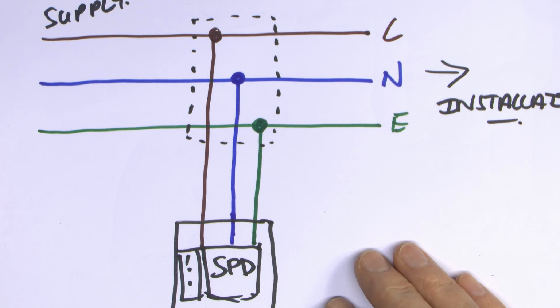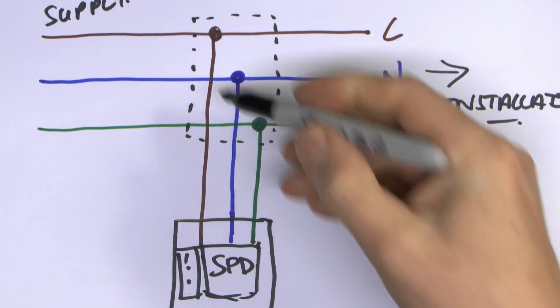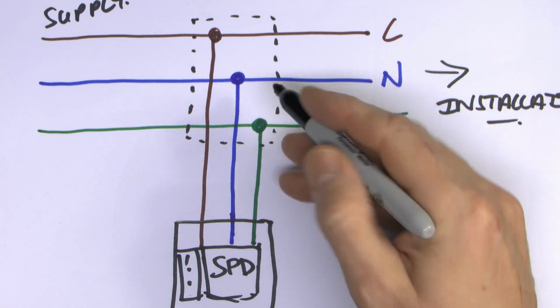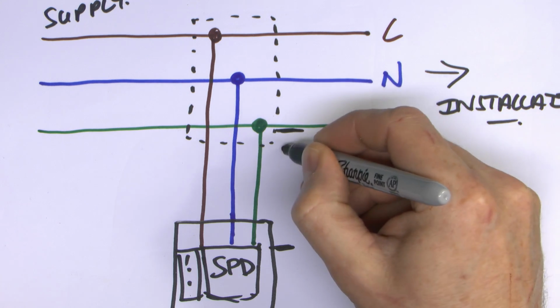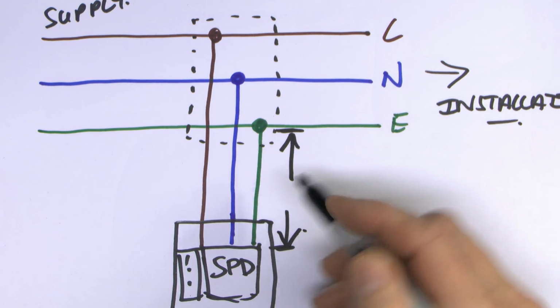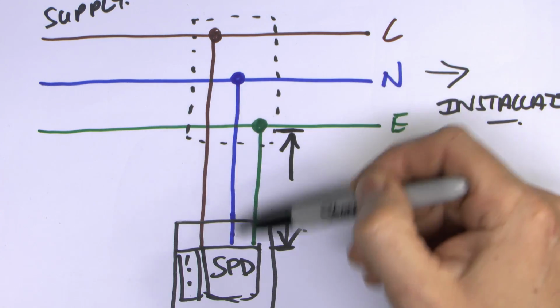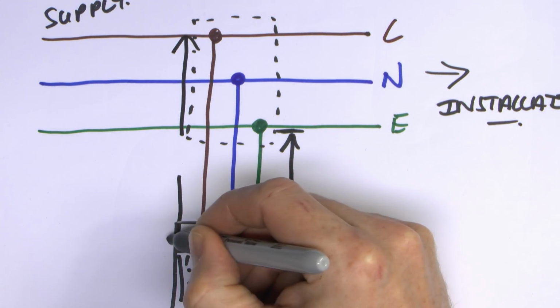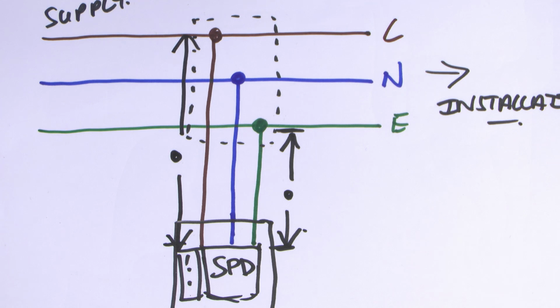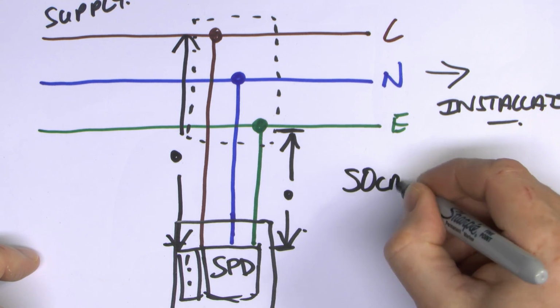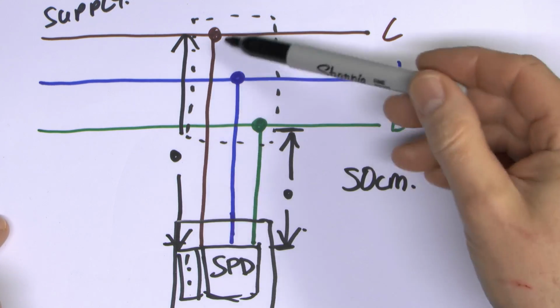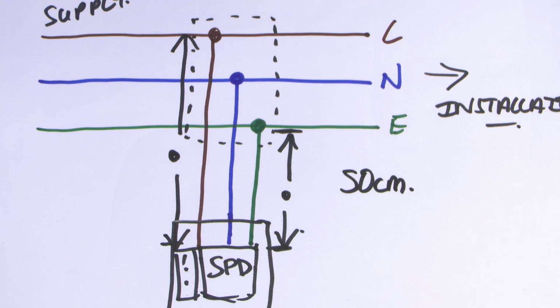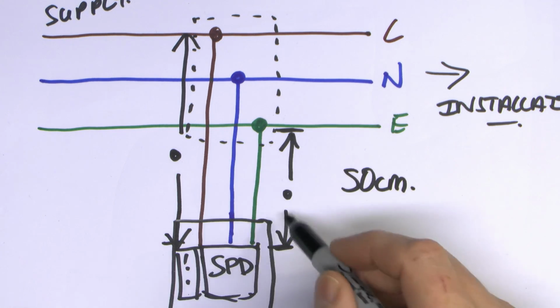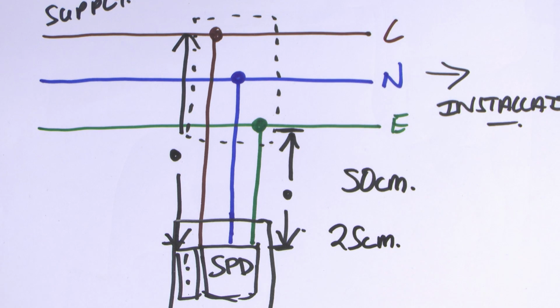Now this is a fairly poor way of connecting it, and the length that we're looking at in this case is the length of these wires. So it's the length of the protective conductor, from here to here, and also the length of the live conductor as well, so that would be either the neutral or the line. The line is longest here, so we'll use that one, and that would be the length to there. So I've got one length here and one length here, and it's the two of those added together. Bearing in mind that the maximum was 50 centimetres, it's pretty easy to see straight away that we've probably exceeded that by a huge amount, because 50 centimetres is pretty much nothing, and if these were the same length each, that means each of those would only be 25 centimetres absolute maximum.